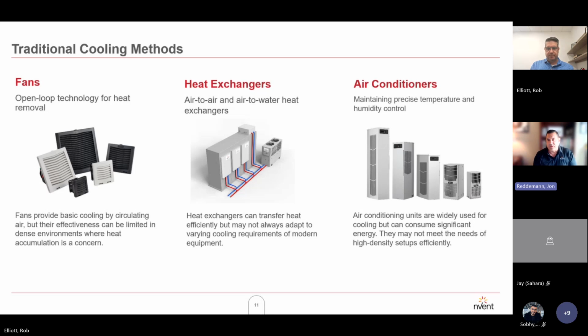Now, jumping ahead a little bit. Water cooling is extremely efficient as compared to air cooling, right? Yeah. When you're looking at a chilled water system, water has a 25 times greater ability to transfer heat than air does. So we can get a much higher cooling capacity in a much smaller footprint using an air-to-water heat exchanger, but we need to have chilled water supply available to us, whether that's through plant process or through an industrial chiller. That's the caveat, right? And we do have to get that piped into the system somehow, whereas air-to-air heat exchangers and air conditioners are standalone systems.